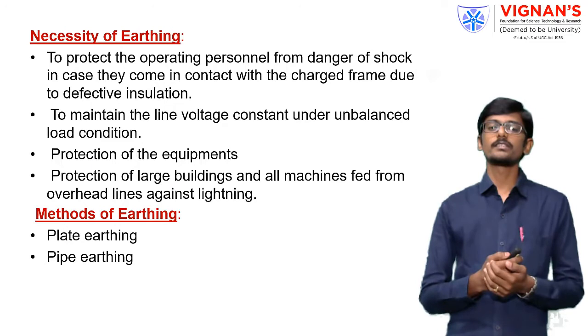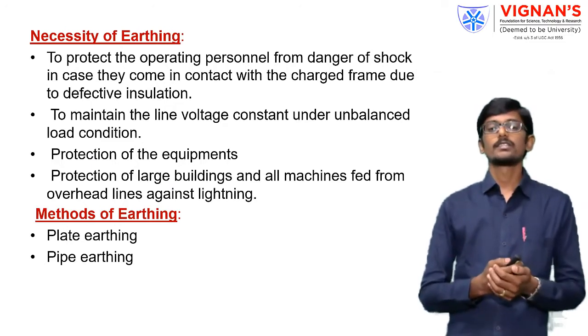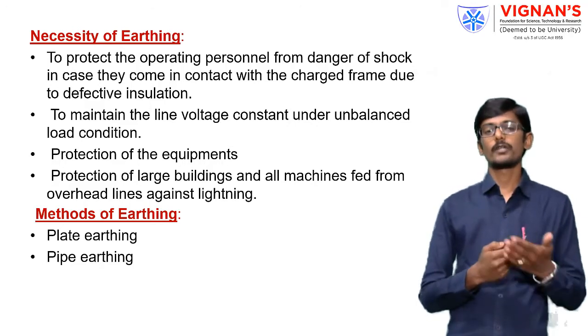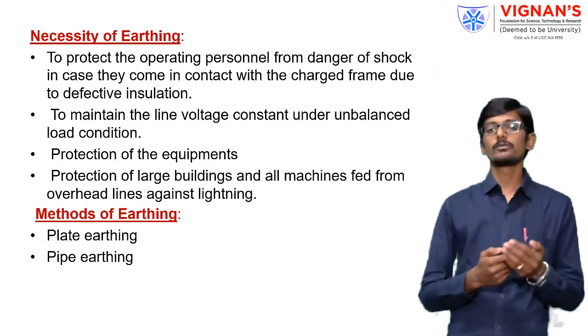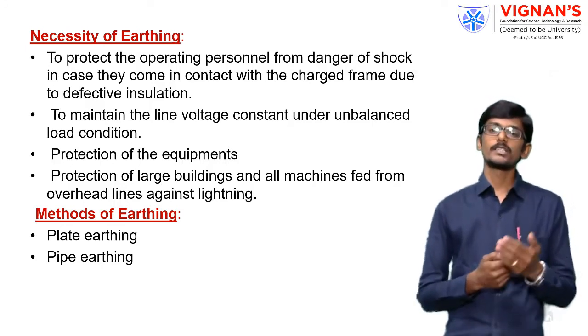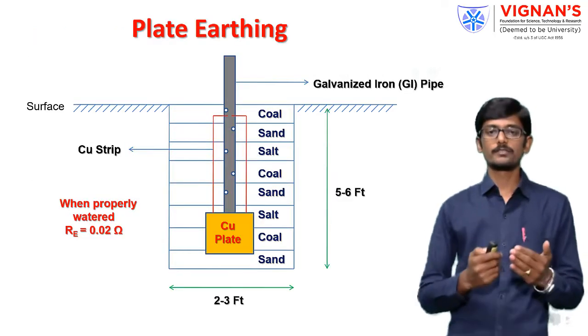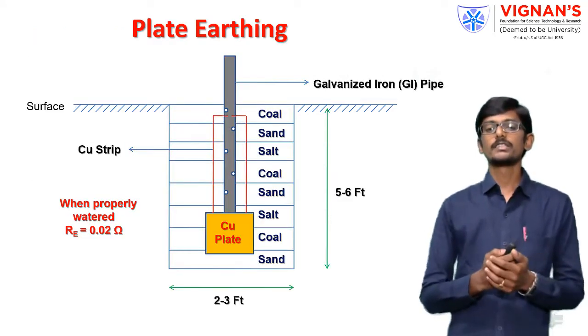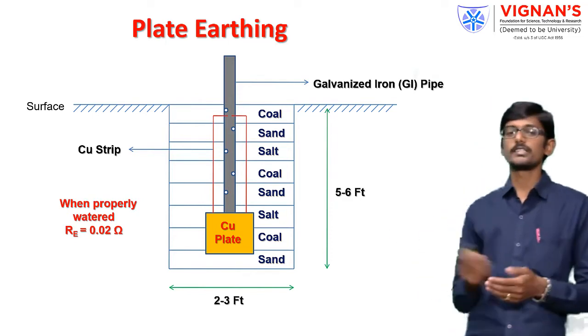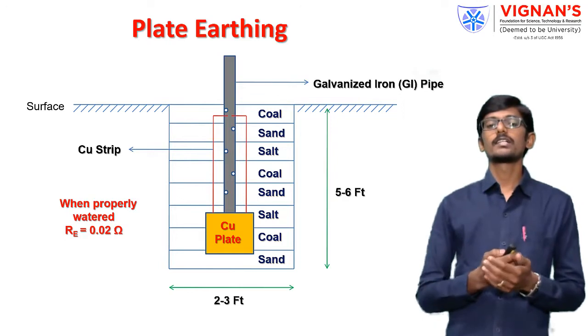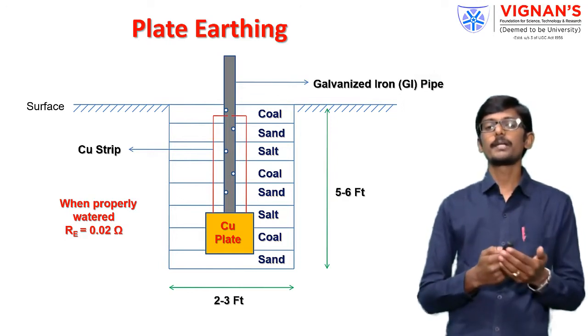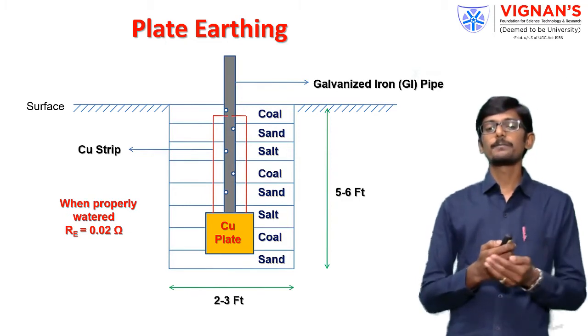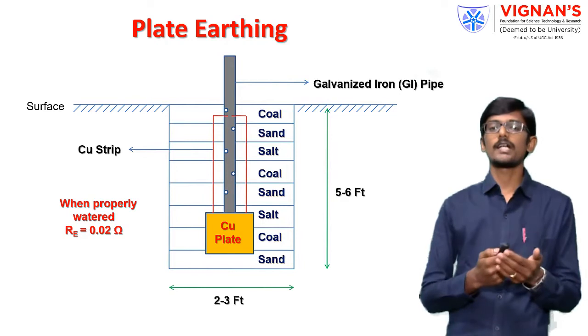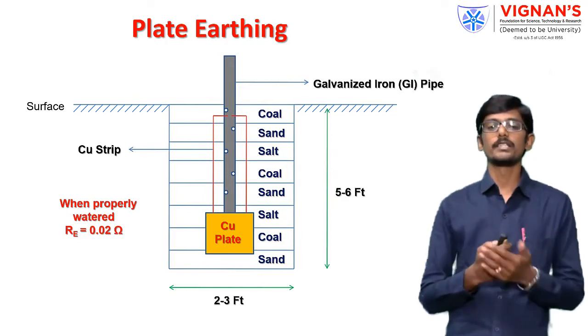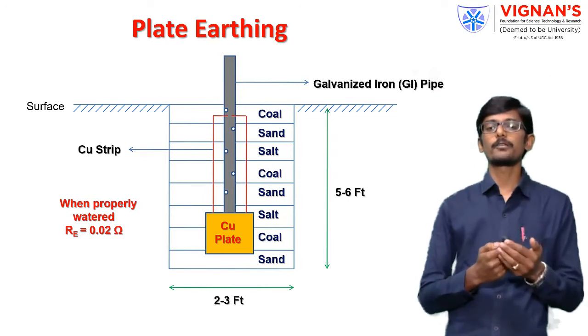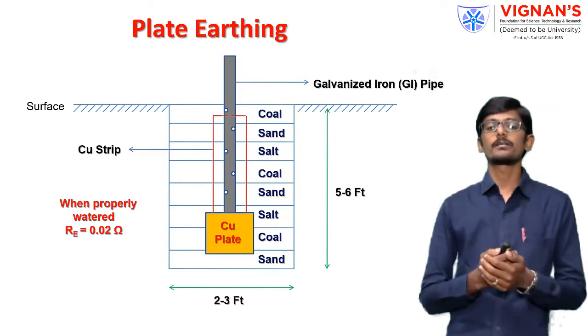So these are the necessities of earthing, in order to protect the human and also devices from faulty conditions or faulty insulation. Earthing is necessary. How we are going to do the earthing: there are 2 types of earthing, plate earthing and pipe earthing. As the name indicates, plate earthing has a copper plate which is buried under the ground. In this figure the copper plate is under the surface and is connected with a GI pipe, that is, a galvanized pipe. The pipe and copper plate are placed in layers of coal, sand and salt in order to reduce the resistance. This type of earthing, where we use copper plates, is called plate earthing.